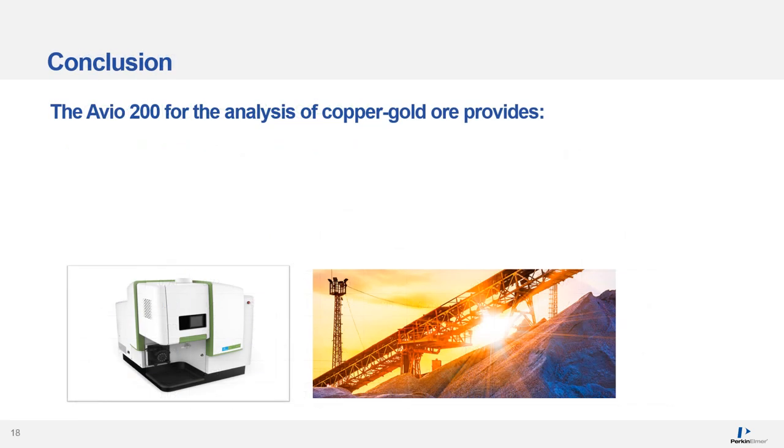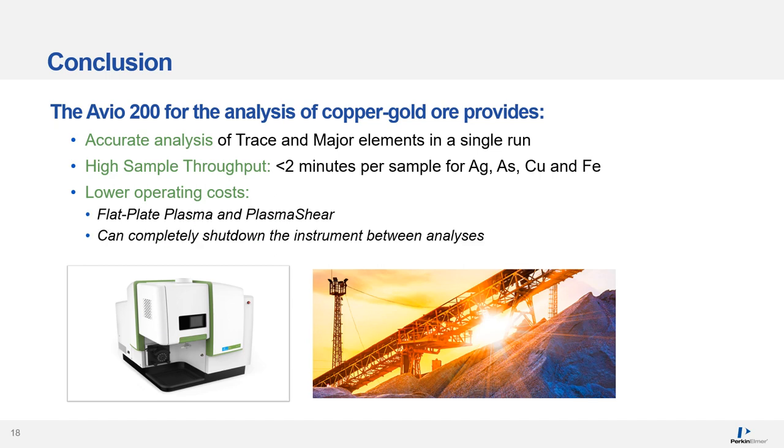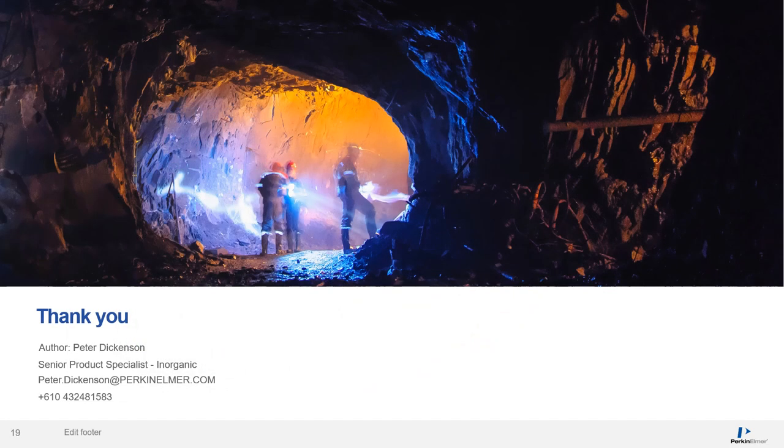In summary, the Avio 200 for the analysis of copper gold ore provides a number of benefits, including accurate analysis of trace and major elements in a single run, high sample throughput of less than two minutes per sample for four elements, and lower operating costs due to the flat plate plasma, plasma shear, and the ability to completely shut down the instrument between analyses. Thank you for listening.